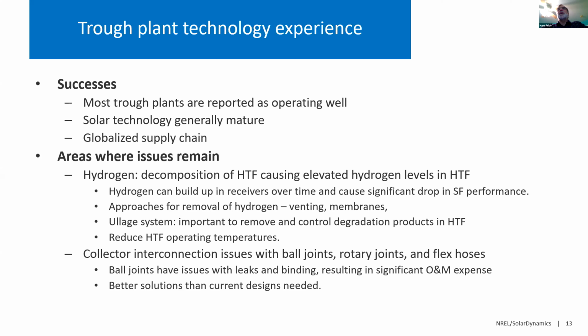Probably the most important one that has been starting to surface in recent years is the question of hydrogen. Hydrogen is caused by decomposition of the heat transfer fluid used in the solar field. As the heat transfer fluid breaks down, it breaks into high boilers and low boilers, and hydrogen is one of those low boilers that gets into the heat transfer fluid. The reason this is a problem is that over time, the hydrogen can migrate through the stainless steel receiver tubes as the oil is flowing through the receiver into the vacuum space.